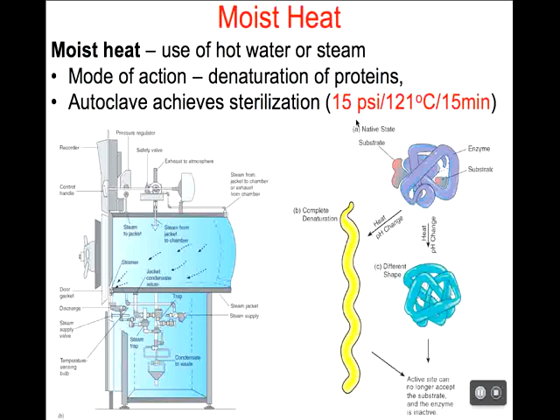And how hot do you have to get in order to truly kill off even spores? You have to get to 121 degrees Celsius, and you do that by getting to 15 psi pressure for about 15 minutes. Now the time depends on how much stuff you have in the chamber, but about 15 to 30 minutes is pretty standard. So in order to achieve sterilization, you can use moist heat, but you have to use an autoclave that gets up to 121 degrees Celsius at 15 psi, and it kills by denaturing proteins.